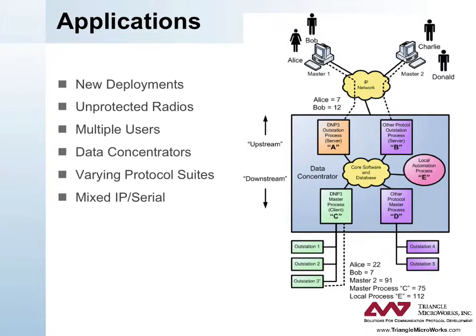Multiple users: in networks like the data concentrator system pictured here, DNP3 Secure Authentication permits a separate identifier to be assigned to each user at the master — for example, Alice or Bob — so that the operations performed by that user are tracked throughout the system. Data concentrators: the specification has rules defined to ensure end-to-end security even through a data concentrator such as the configuration pictured here. Varying protocol suites: DNP3 Secure Authentication operates at the uppermost protocol layer and is therefore carried across networks that use different lower-layer protocols. Mixed IP and serial: DNP3 Secure Authentication works well with terminal servers and IP-based radios.